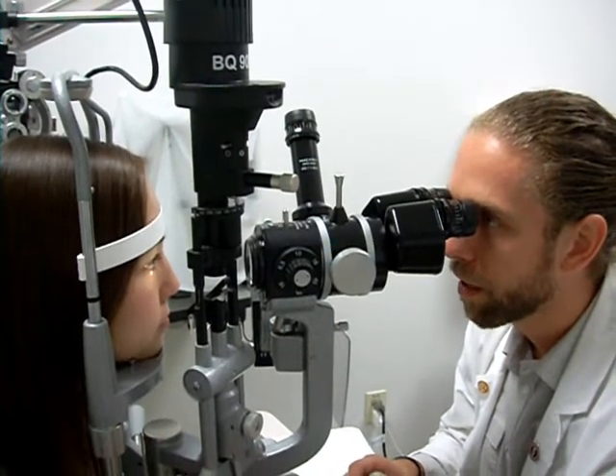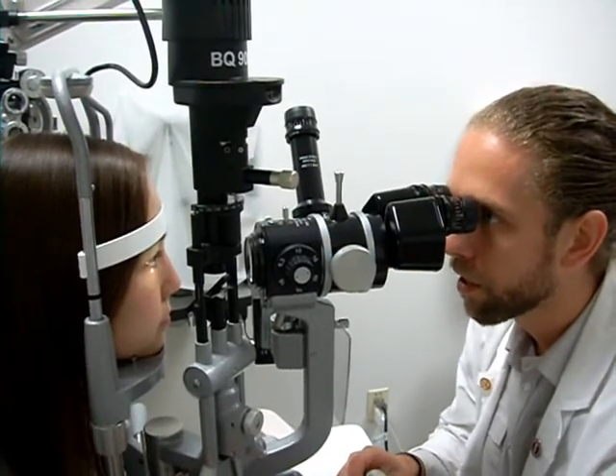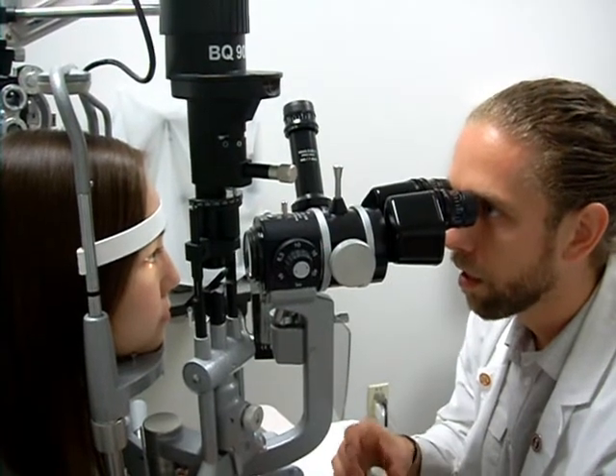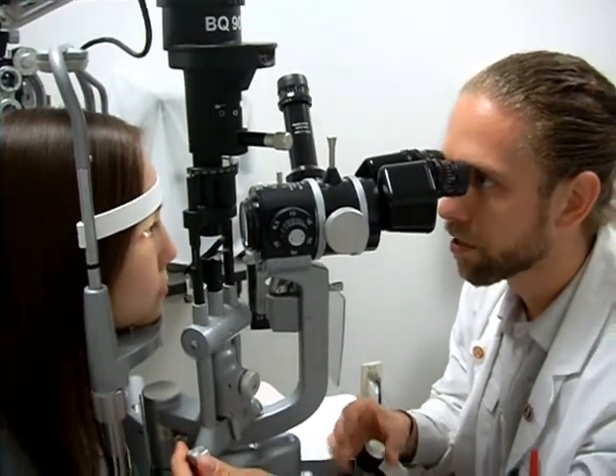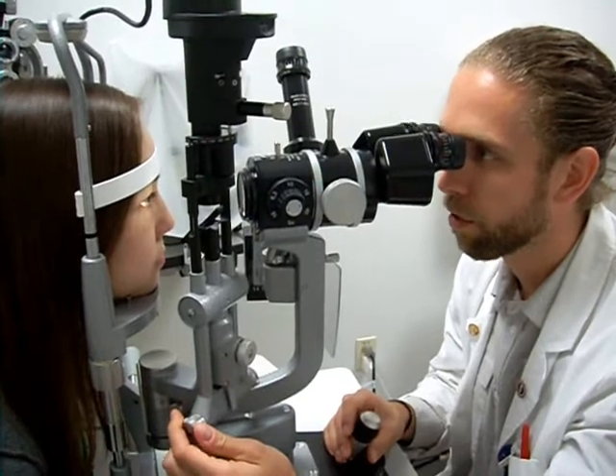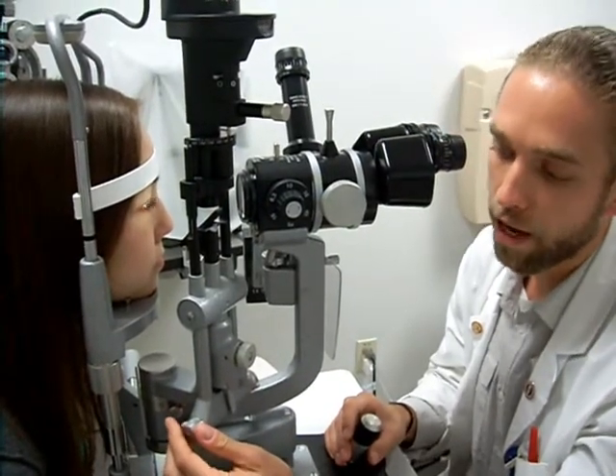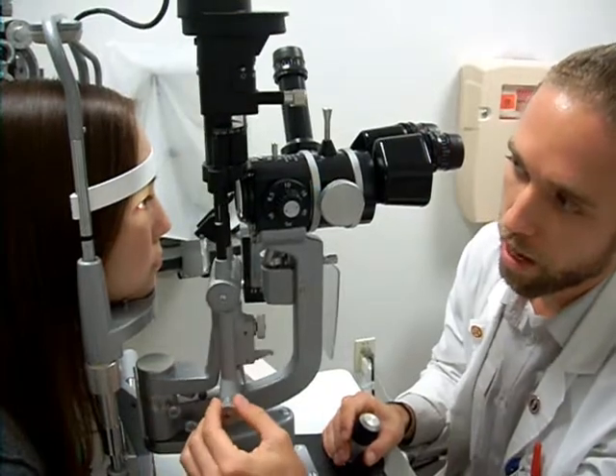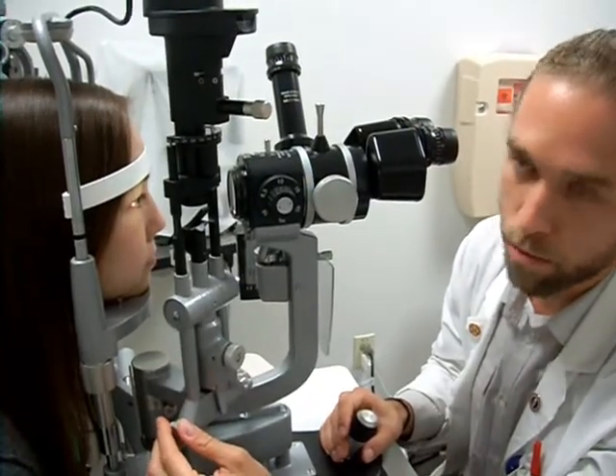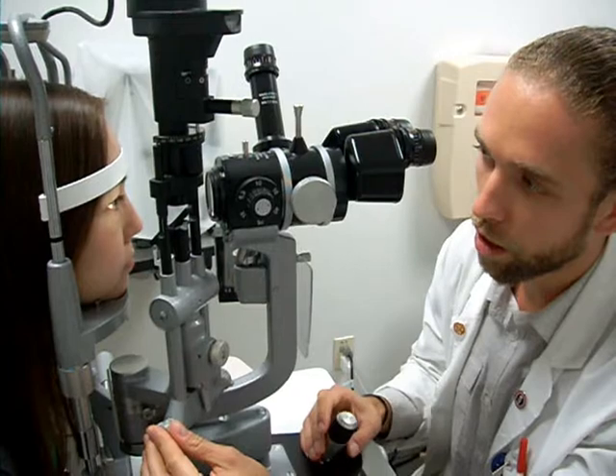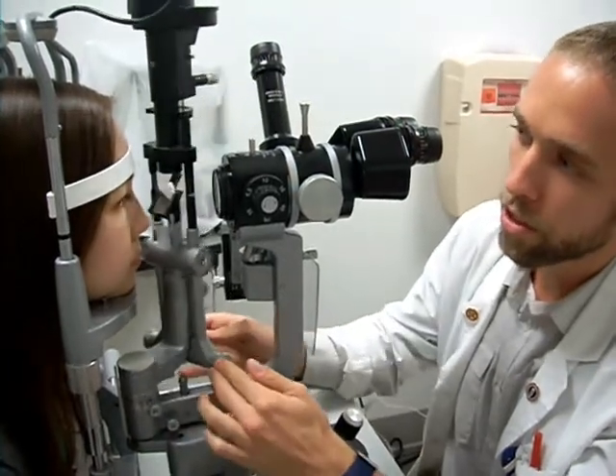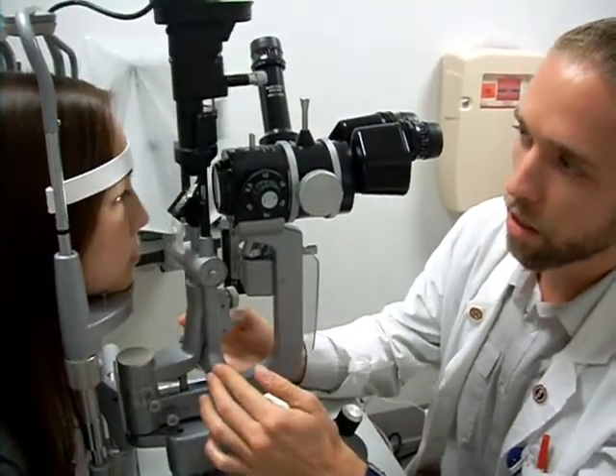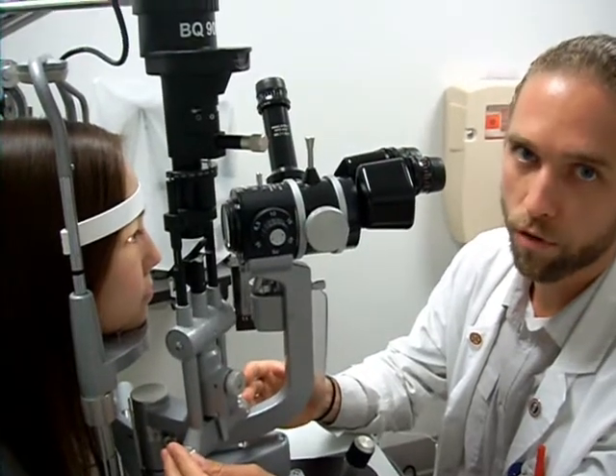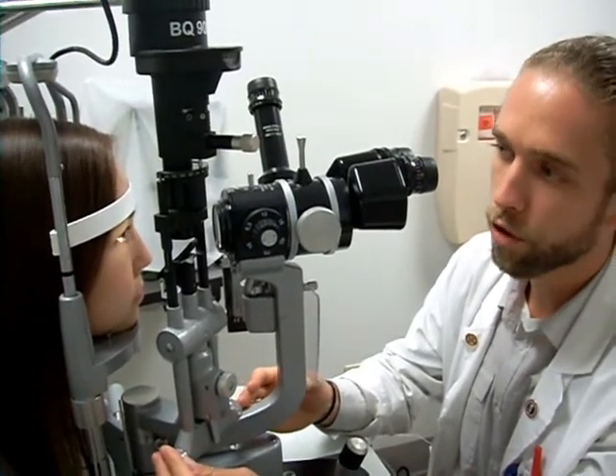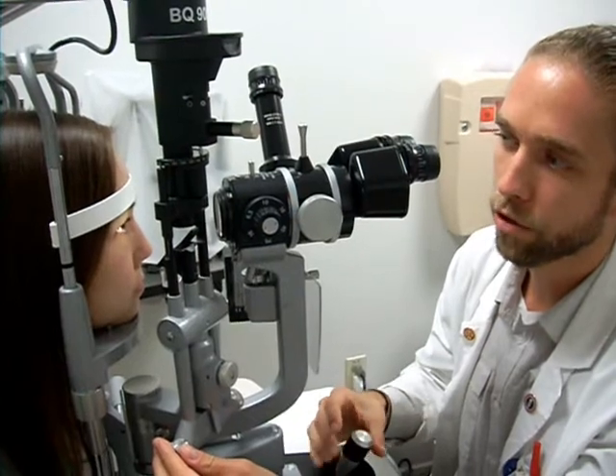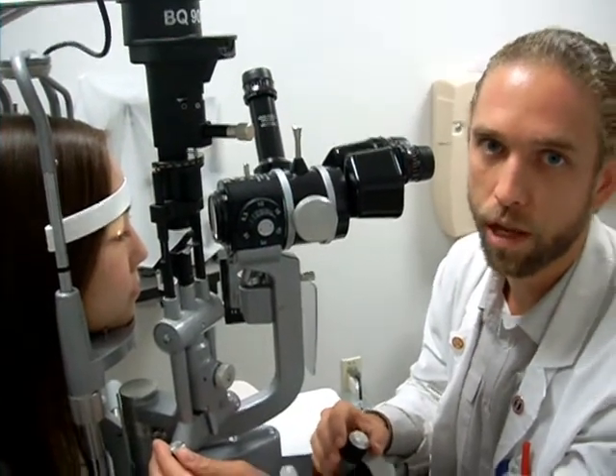So when you're looking through the microscope, you're going to be trying to get the best picture of the eye possible. And one way you can do this is by adjusting not only the position of the microscope, but also the light that's entering the eye. And as you can see, the light and the beam is mobile, and it's on this mobile arm. And you could move the arm and adjust the angle by swinging the arm back and forth across the plane of view, and that will help you get good angles to evaluate the structures in the anterior segment.